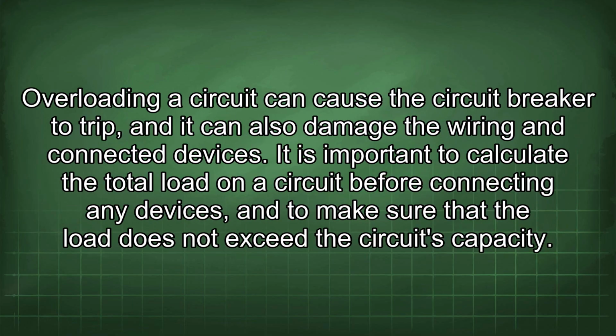Overloading a circuit can cause the circuit breaker to trip, and it can also damage the wiring and connected devices. It is important to calculate the total load on a circuit before connecting any devices, and to make sure that the load does not exceed the circuit's capacity.